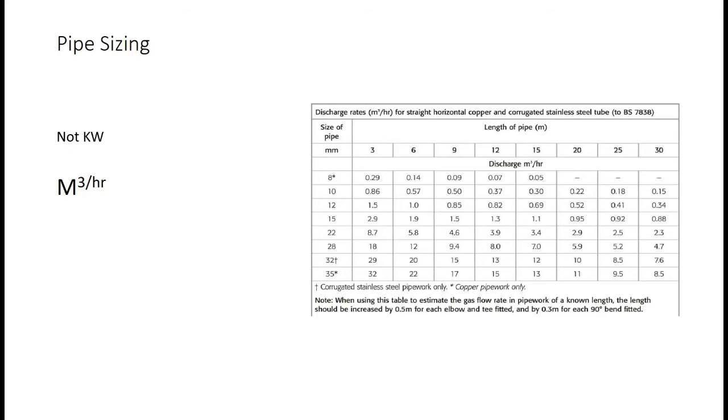Remember when we're pipe sizing we don't use kilowatts in the calculation itself. We have to convert the kilowatts into metres cubed per hour in order to do the calculation. It's very easy to do, you simply multiply the kilowatts by 0.094.